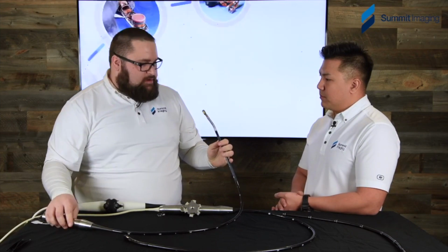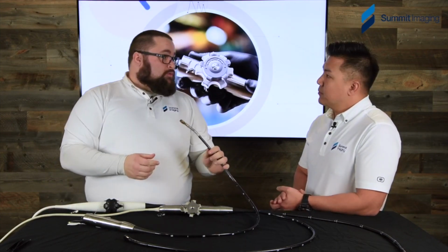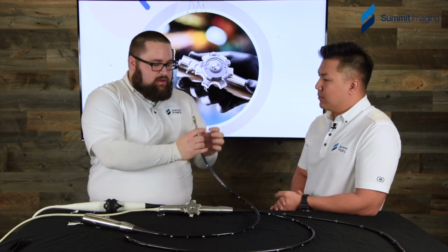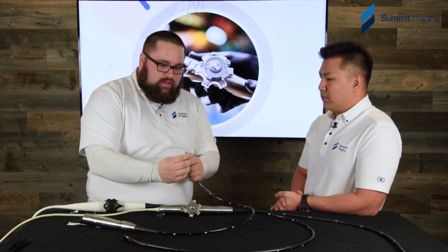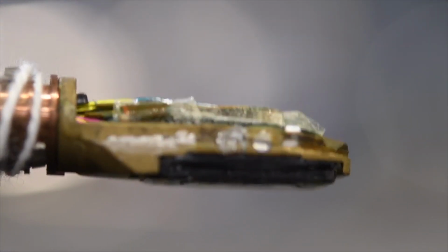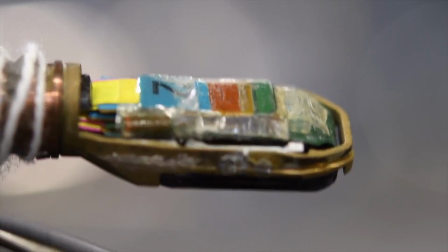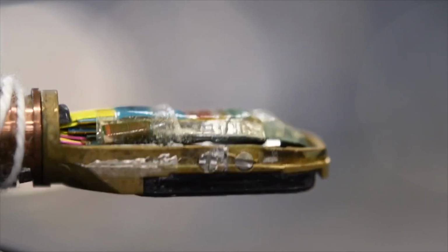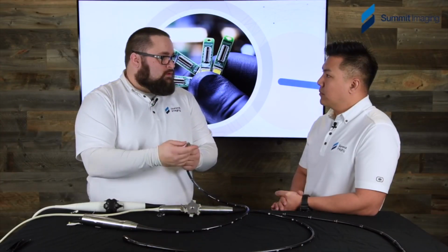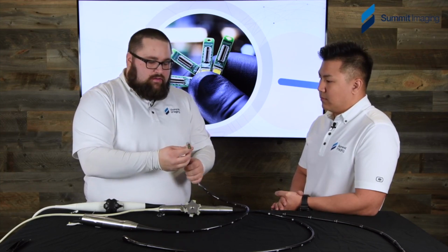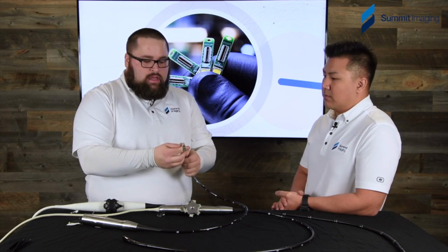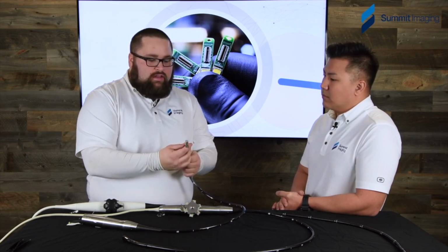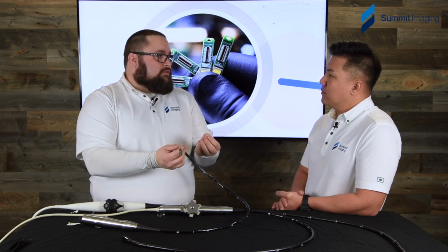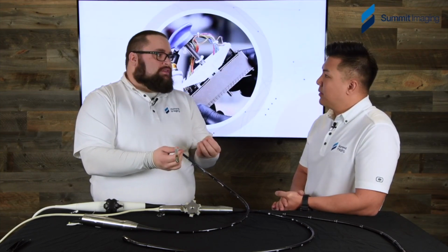Now, this one has had a bit of a rough life, but it does serve as a great example, and we'll actually get some nice close-up shots here in a moment. But we have an array as well as the lines leading to it. Now, these lines are coax lines about the size of your hair. One drop of Cidex solution, OPA, stomach acid, or even some water, and then say it sits for the weekend, this entire head will just be full of rust. All of that would start flaking off. And it's because of a pinhole or maybe a small crack in the head. And when we say fluid intrusion, sometimes it's not massive. It's actually just a drop, but it had the time to sit there and do the damage too.